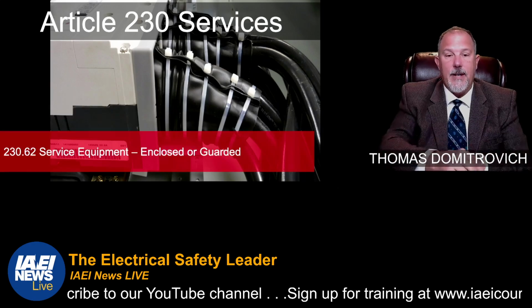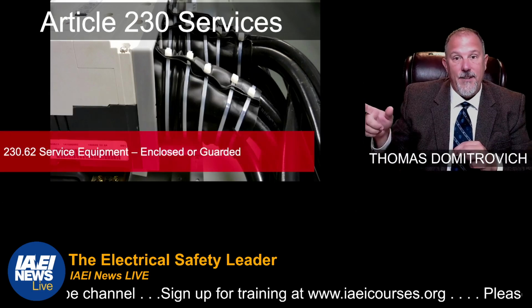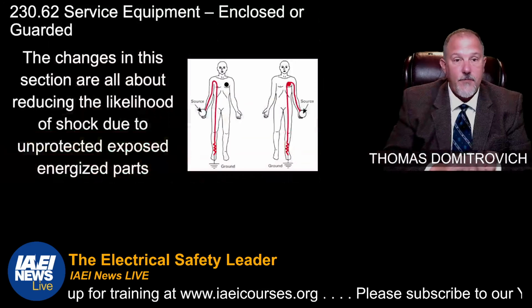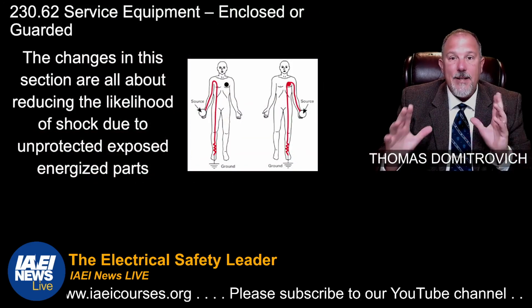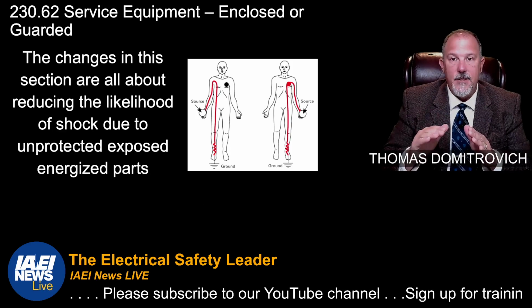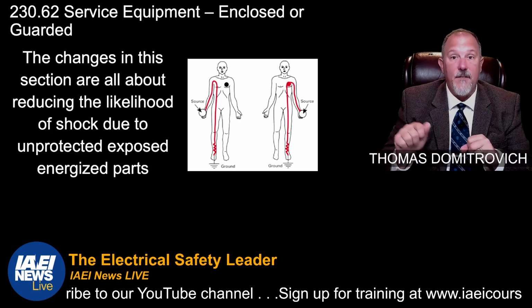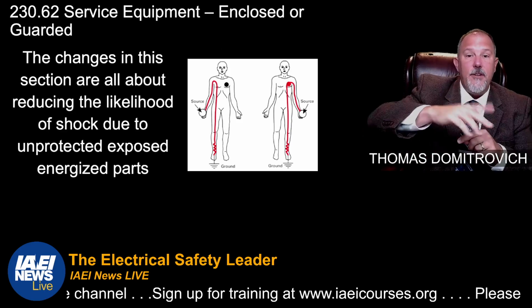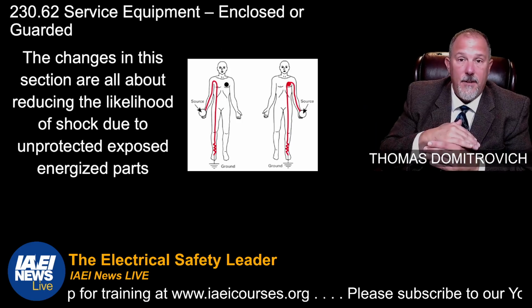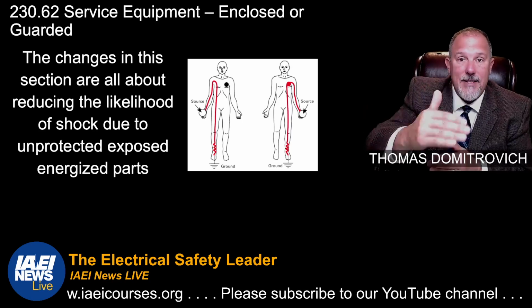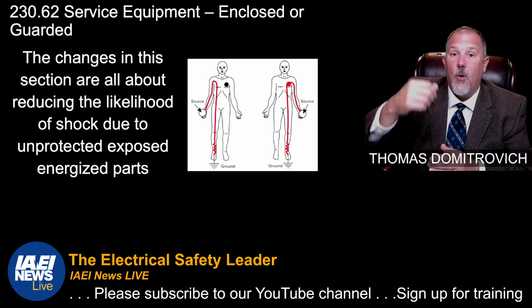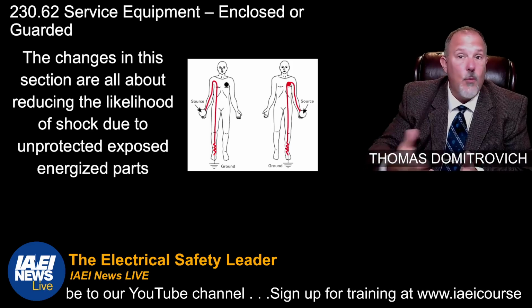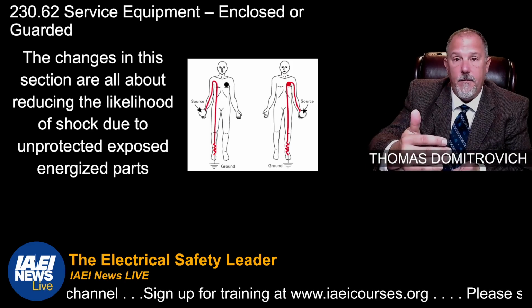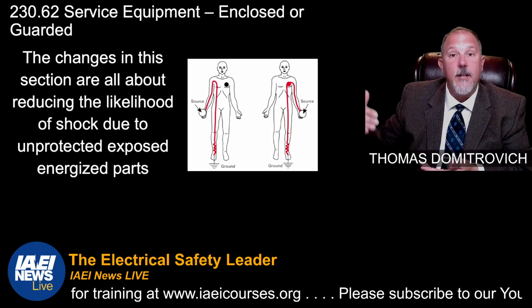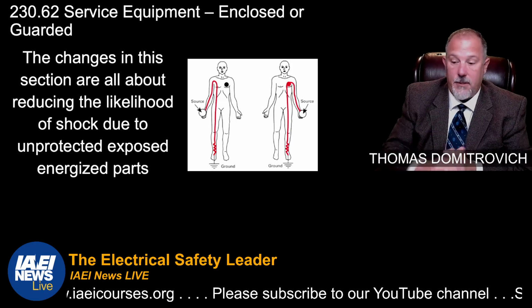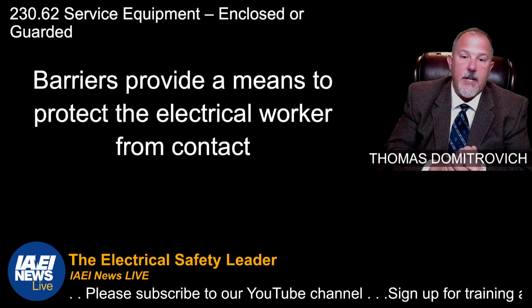So what 230 did was recognize that, and it actually started in 408, where we added the words panel boards when it comes to barriers. This change is about shock, but it does reduce the likelihood of coming in contact with energized parts, even though the main is turned off, because those main lugs are still energized. So I reduced the likelihood of shock. I also reduced the likelihood of an arc flash event. Why is that? Because if I reduce the likelihood of you accidentally coming in contact with energized parts, with either you or a wrench or a screwdriver or a conductor, whatever it is, then I've reduced the likelihood of shock, and I've reduced the likelihood of an arc flash event caused by your actions. So barriers provide a means to protect the electrical worker from contact.